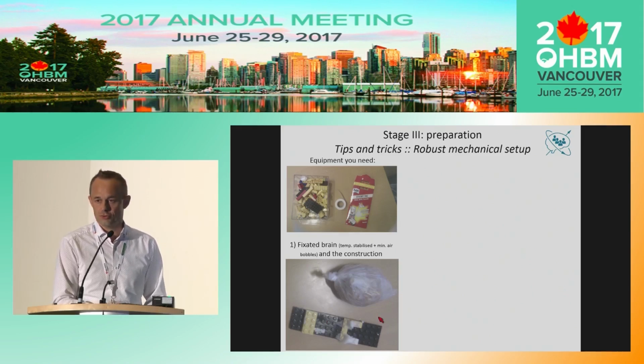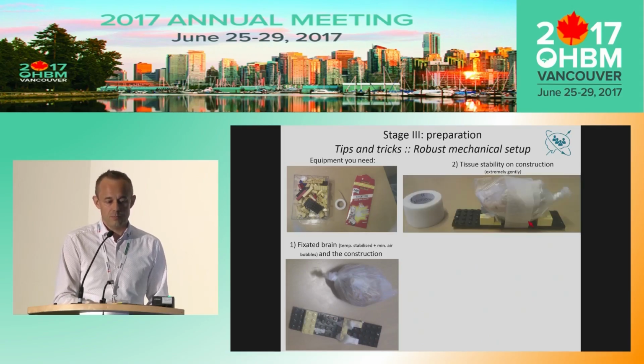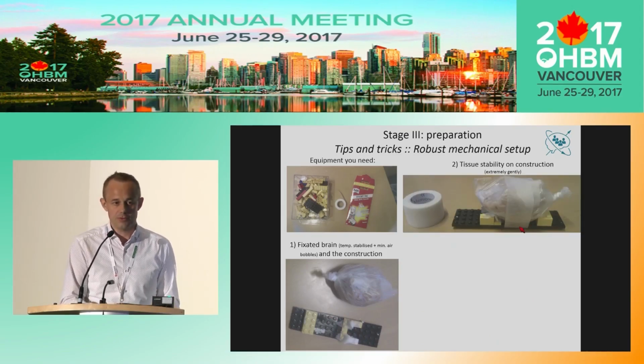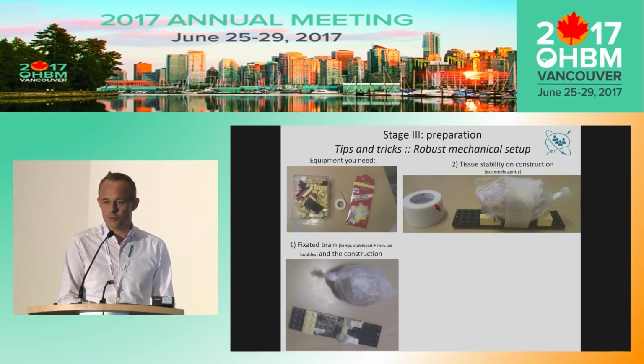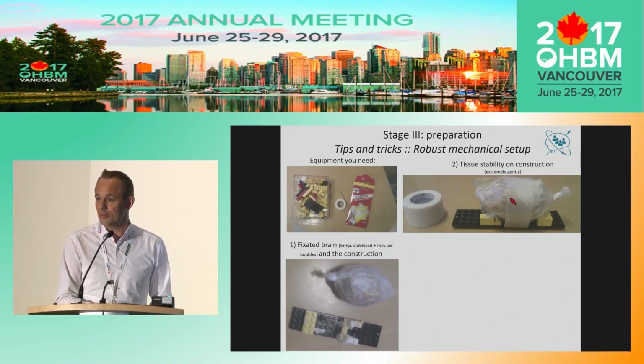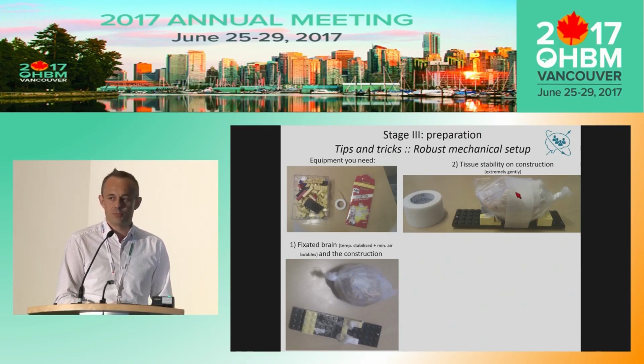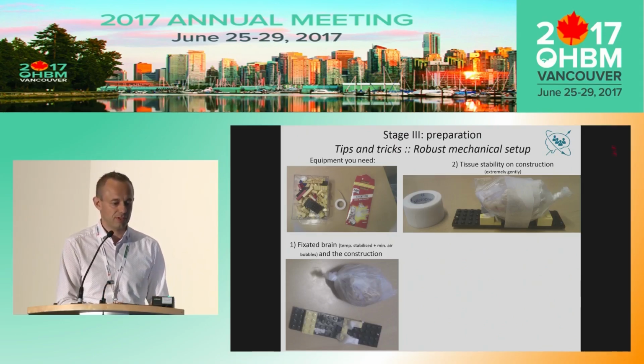You make a small construction that fits into the coil, and then you place your brain upside down on the Lego construction. You take this micropore tape and wrap it very gently around the tissue. It's simply to ensure it is mechanically stable when you're measuring. But please be aware, do not add any force to the tissue, because then you introduce geometric distortions while you're scanning.